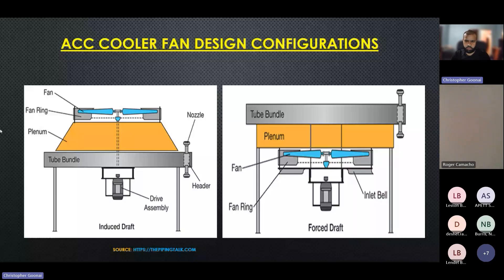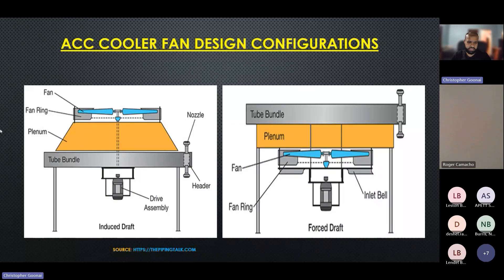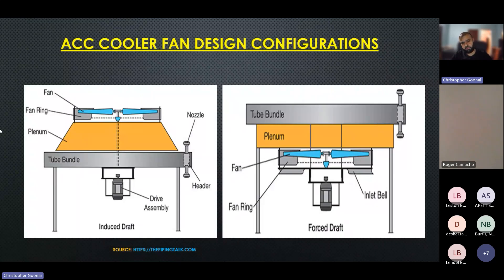There are really two different design regimes that establish flow through the cooling fan or cooler system. On the left here you have the induced draft — these fans are usually mounted above the tube bundle. You could think of it like an extractor fan; it actually pulls the air through the tube bundle and expels it out. On the right you have the forced draft, which pushes the air through the plenum and up through the tube bundle.